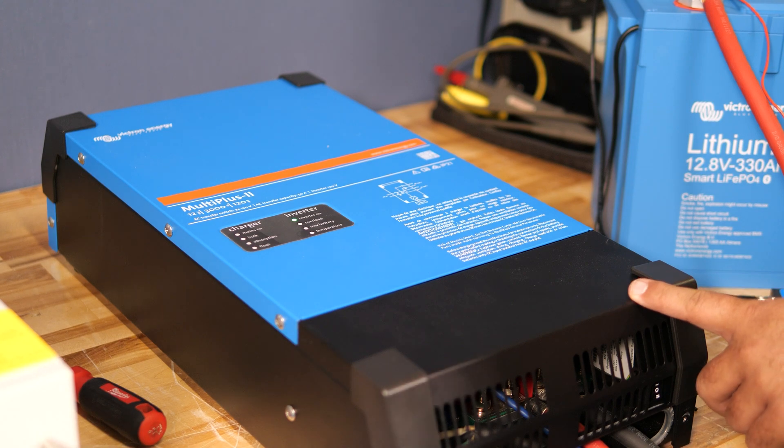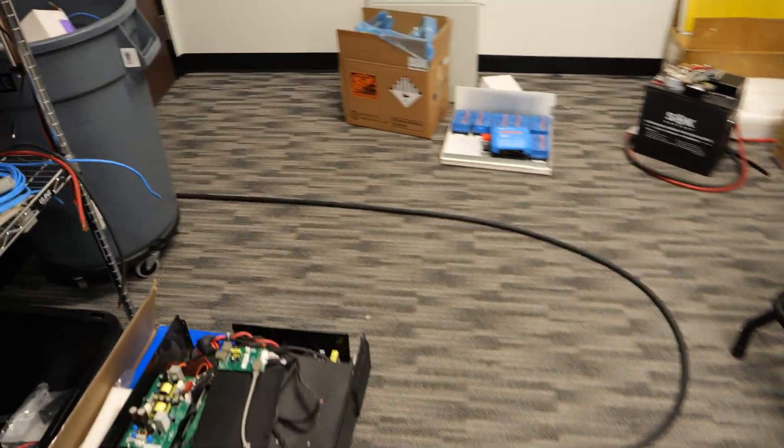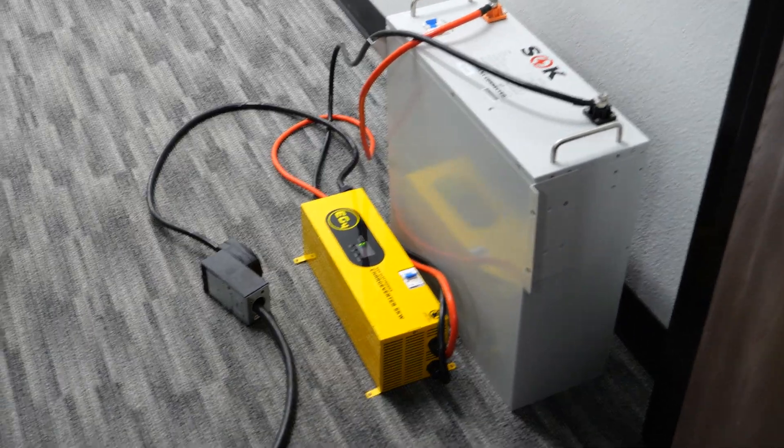Here's the Multi Plus 12 3000. We've got it wired to an AC input. The AC output feeds to our load, which is one of the charge converters, so we can push this unit to the full 2400 watts it can produce.